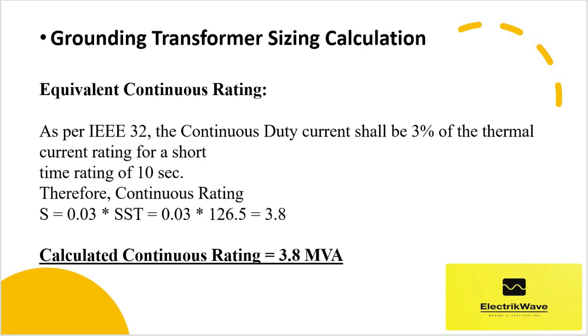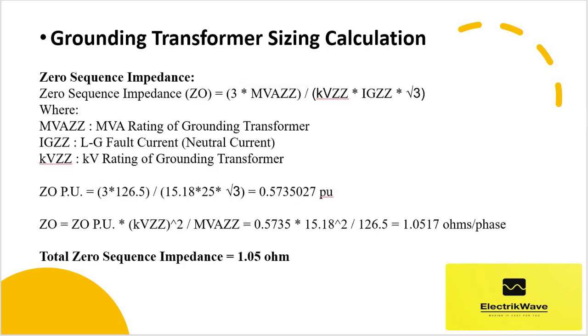Now let's calculate the zero sequence impedance. Zero sequence impedance Z0 = 3 × MVA_ZZ / (kV_ZZ × Ig_ZZ × √3), where MVA_ZZ is the MVA rating of the grounding transformer, Ig_ZZ is the line-to-ground fault neutral current, and kV_ZZ is the kV rating of the grounding transformer.